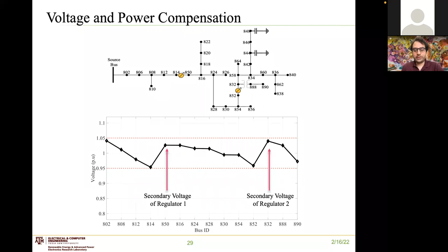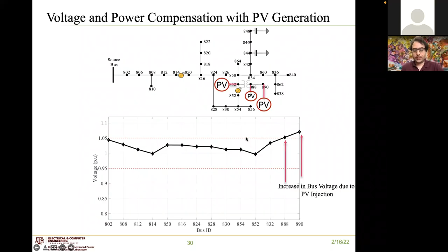So what happens when we have distributed generation in the form of distributed rooftop photovoltaic generators? So here is the same feeder. The difference is that now we have connected some PV generators at the far end of the feeder, and we redo the power flow to determine the voltages at each of these buses. And we find that the buses where we have connected these PV generators, the voltage has increased. And in fact, in 2 of those buses, we have voltages that are outside acceptable limits. So sure, we can always control the settings of these regulators to make sure that our voltage always stays within this bandwidth. But if you have enough distributed generation on this feeder, at some point, the regulators will not be able to correct for that voltage, as is happening in this case.